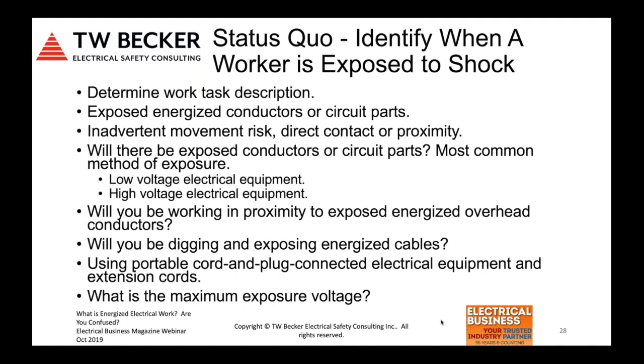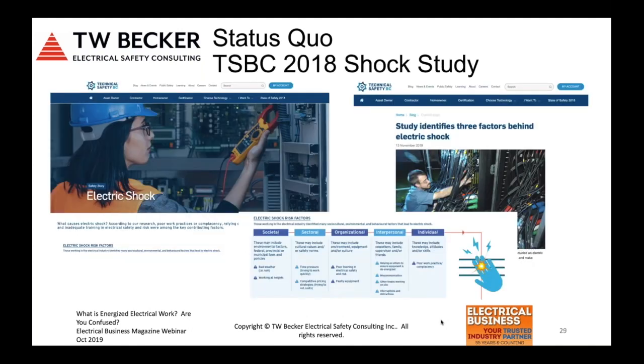So again, low voltage, high voltage, exposed conductors and circuit parts: different workers, different qualification and training, different procedures, different techniques, different application of PPE tools and equipment when we apply the risk control methods to reduce risk. Working within proximity to exposed overhead power lines and conductors involves a multitude of different workers, non-electrical workers, digging and inadvertently exposing energized cables, using portable cord and plug connected electrical equipment, extension cords. That's a whole non-electrical worker discussion. We haven't done a very effective job in industry with non-electrical workers and shocks related to using that equipment. And again, after that, what's the maximum exposure voltage? What's the maximum voltage on this electrical equipment and the conductors and circuit parts that are exposed?